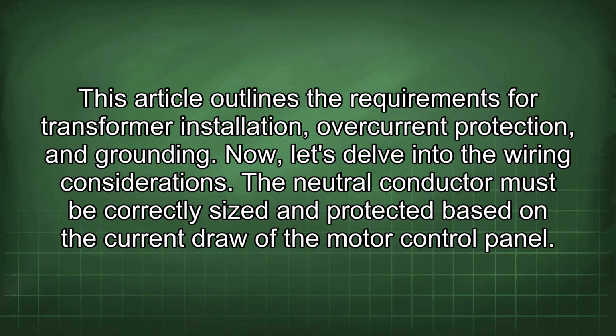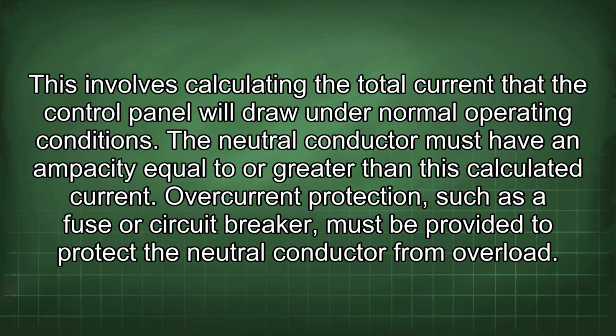Now let's delve into the wiring considerations. The neutral conductor must be correctly sized and protected based on the current draw of the motor control panel. This involves calculating the total current that the control panel will draw under normal operating conditions. The neutral conductor must have an ampacity equal to or greater than this calculated current. Overcurrent protection, such as a fuse or circuit breaker, must be provided to protect the neutral conductor from overload.